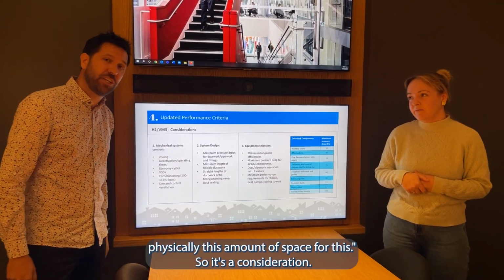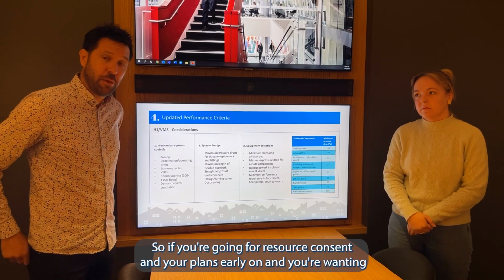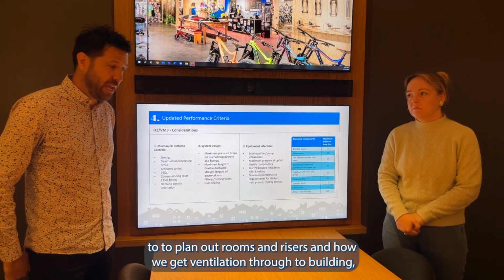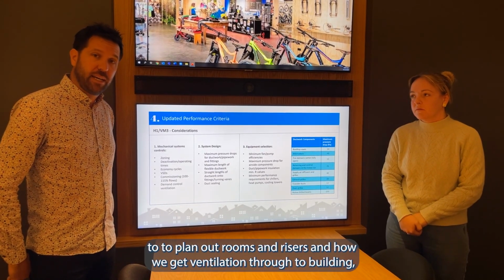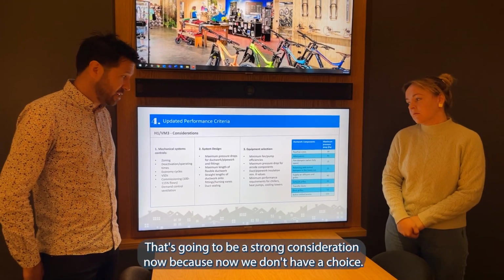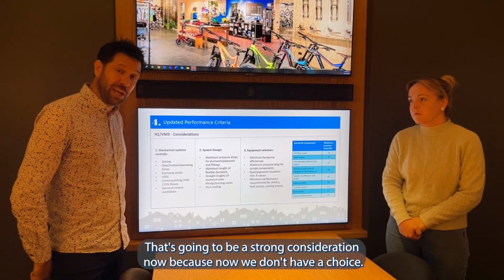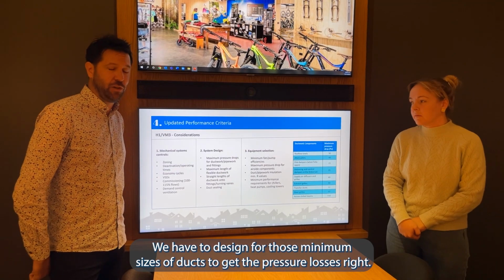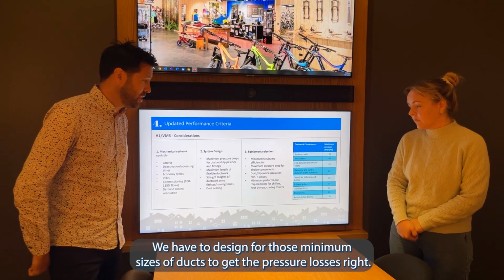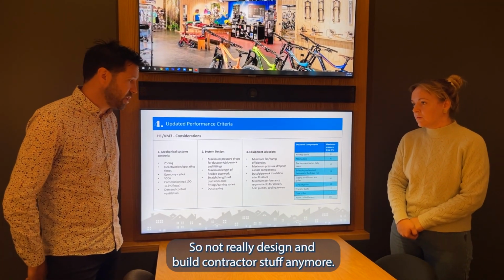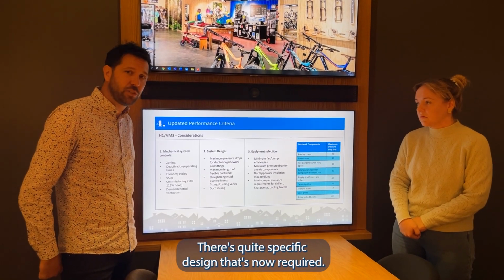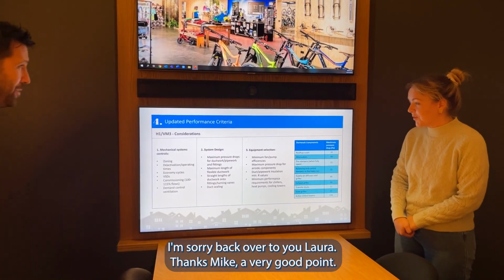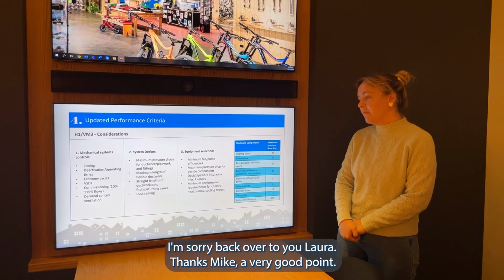So it's a consideration. If you go for resource consent, and you planned early on and you're wanting to plan out your rooms, your risers, how we get ventilation through the building, that's going to be a strong consideration now, because now we don't have a choice. We have to design for those minimum sizes of ducts to get the pressure losses right. So it's not really design and build contractor stuff anymore. This is quite specific design that's required. So, sorry, back over to you. No, that was a very good point.